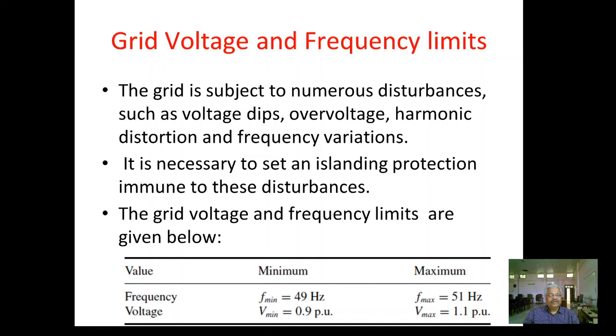Now we have set these values for UV, OV, UF, OF protection, but still there is a problem, and we call it the non-detection zone, NDZ. Here, for delta P and delta Q values inside this region, you cannot detect the opening of a circuit breaker of a utility, and you will be unaware of what happened, and there is a chance of unintentional islanding.